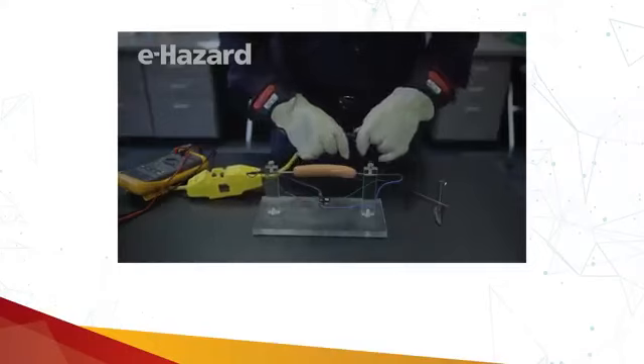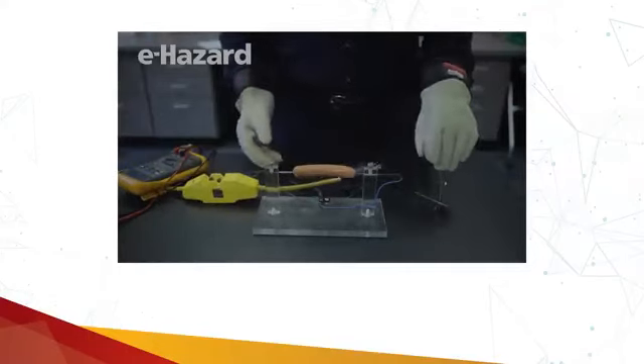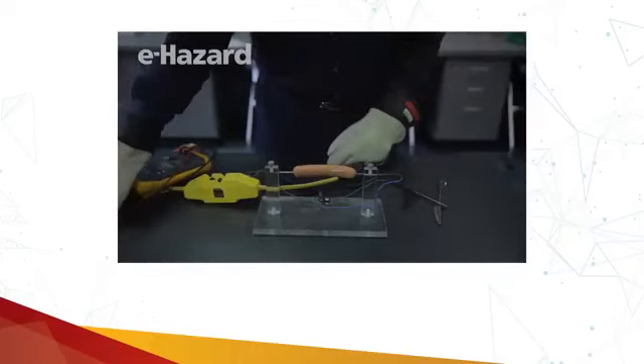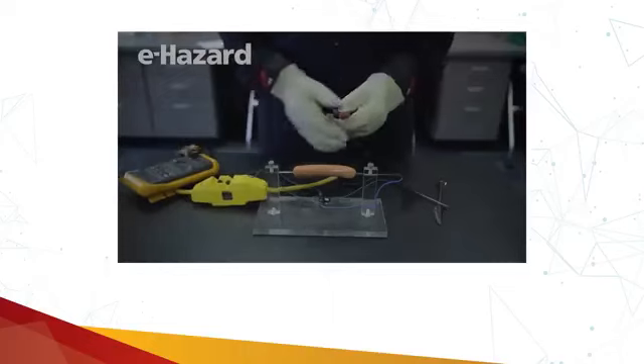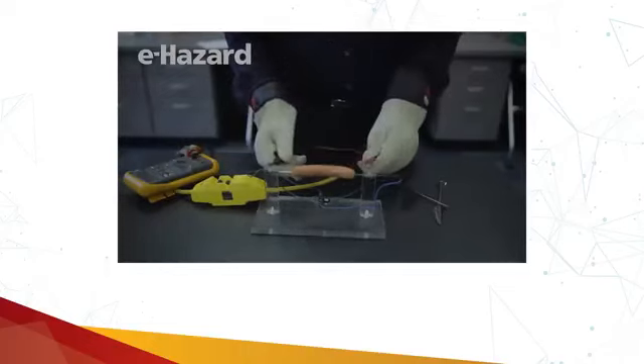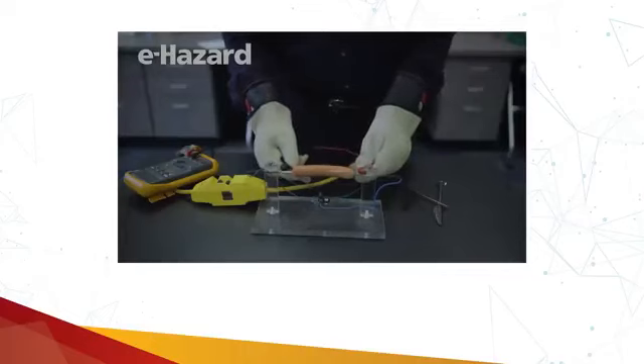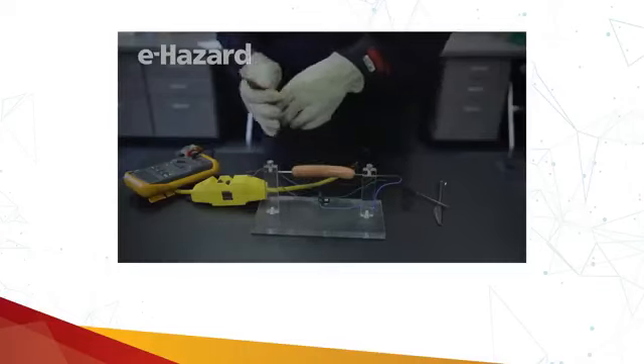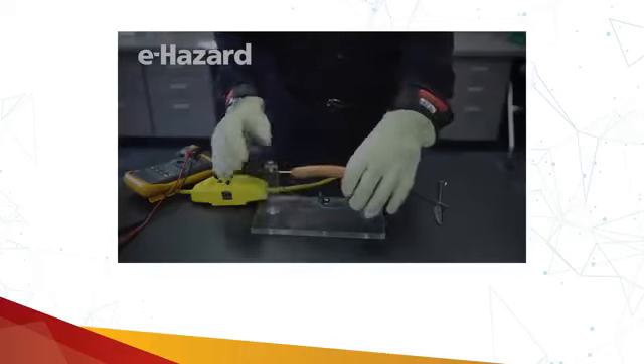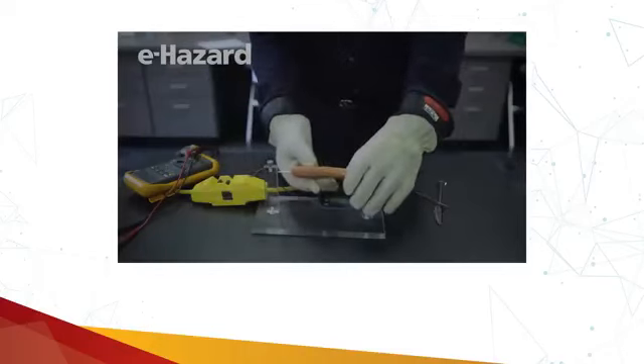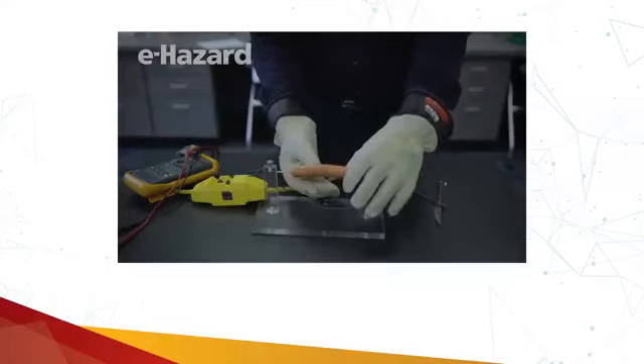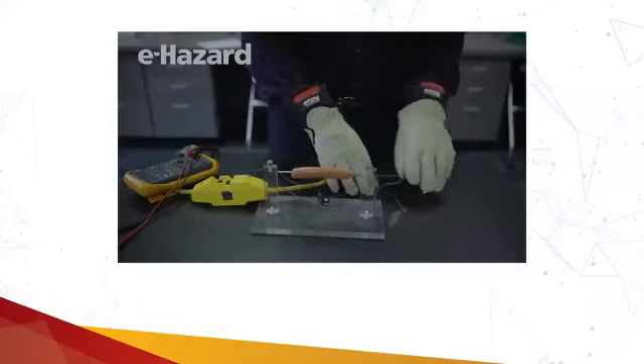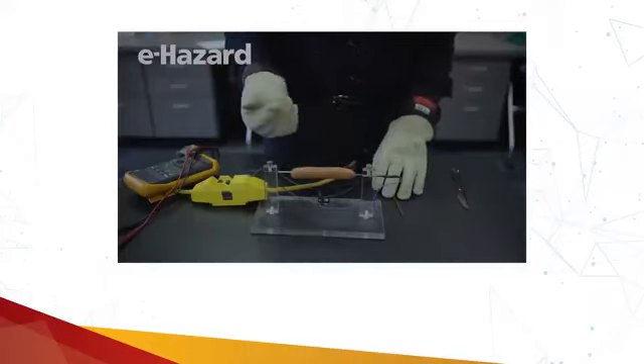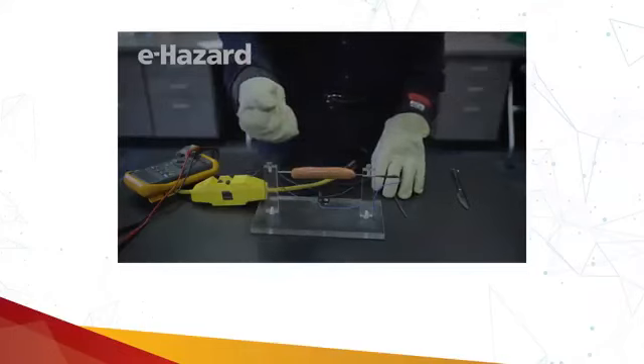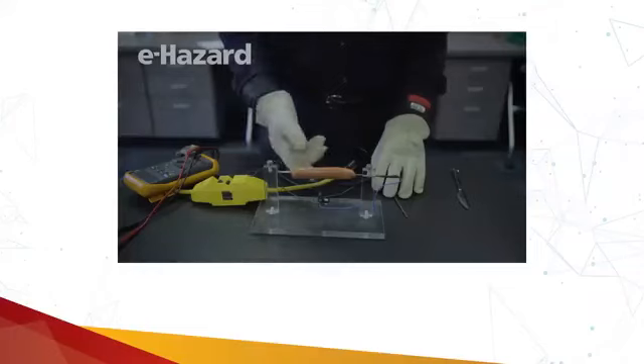All right, so we're going to plug Charlie in. And what do we see? Absolutely nothing. So let's take our voltmeter and let's just see how much voltage we're putting on Charlie. So I put it across the two terminals and I measure 120 volts, right on 120. Do you see anything happening with the hot dog? Nothing. Nothing is going on. Now this, because the ground is disconnected, represents you with a drill that somebody cut the ground pin off on. And it shorts out, and now you're laying on the ground, held onto this drill, and you can't let go, and you're getting cooked like Charlie.